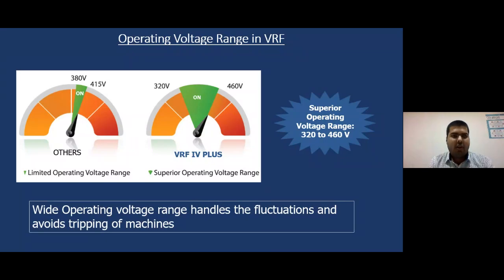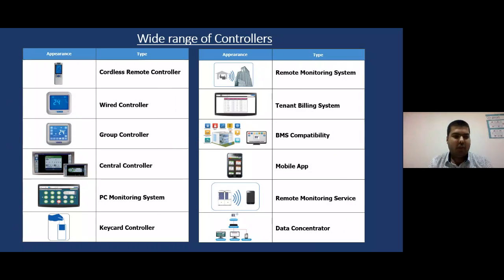And what is the wide range of controllers which a VRF can use? There are standard corded and cordless controllers, but you can also group various machines together to have a group controller, and observe which machines are working and which are switched off through a PC monitoring system. Some companies also have a remote monitoring system. If an installation is, say, 1000 HP or 1500 HP, a person sitting far away in Mumbai or Chennai can look at your machine through internet connectivity and observe which machines are working and how they are working. It is a very unique feature.